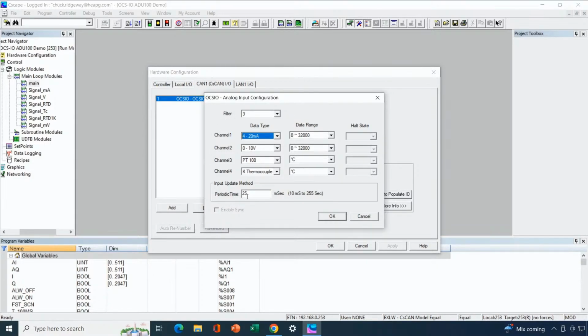Okay, we're going to skip all the way down to the bottom now and talk about this one here, which is the input update time. And that is in milliseconds. It can range as fast as 10 milliseconds and go up from there. I've set it to 25 milliseconds. What is this? Well, this is how often the ADU 100 is going to send new readings over CAN to the OCS controller. So that's what that's for. So you can, again, adjust that for whatever speed you need. 25 milliseconds is a pretty good response time here. Okay, and then we have our channel by channel configuration for our signal and sensor type as well as our data range.